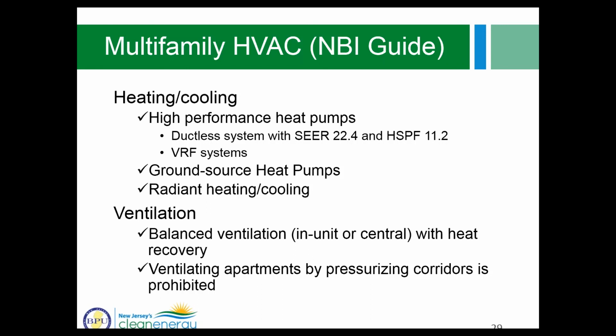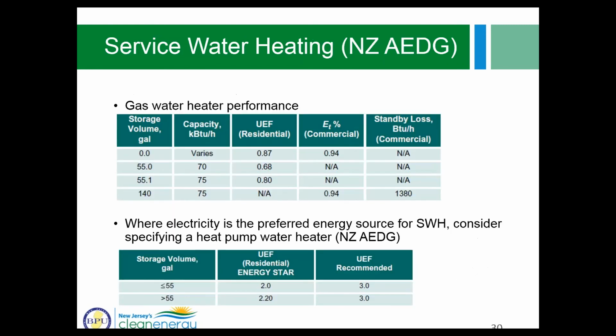It's important to remember that ventilating apartments by pressurizing corridors is prohibited. It conflicts with ASHRAE Standard 62.1. So you can't pressurize corridors, you can't supply outdoor air to corridors, anticipating that it will also provide outdoor air to apartments through undercuts under the entrance door. So again, this is not an allowed option.